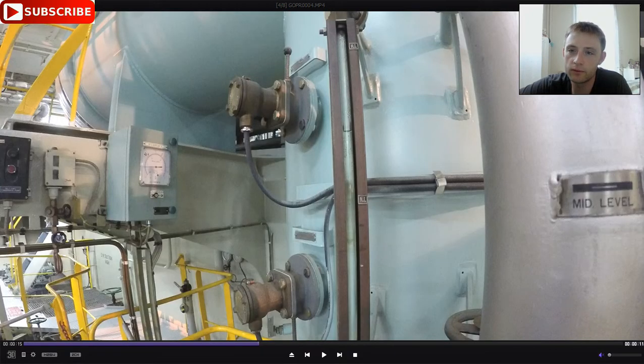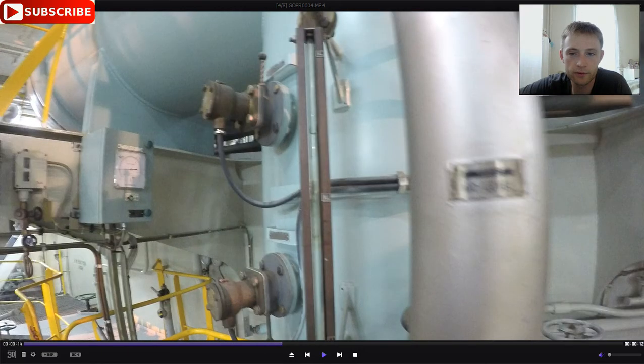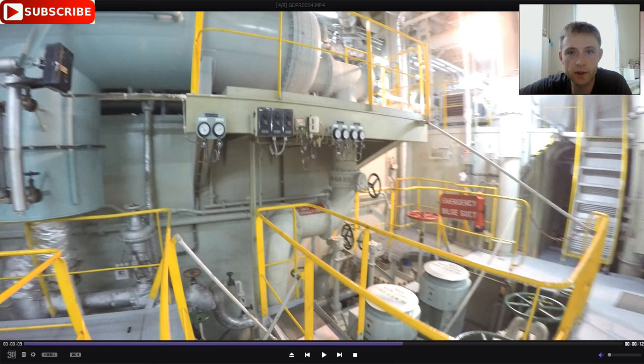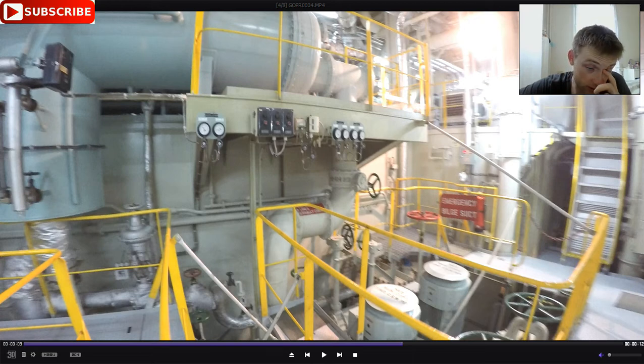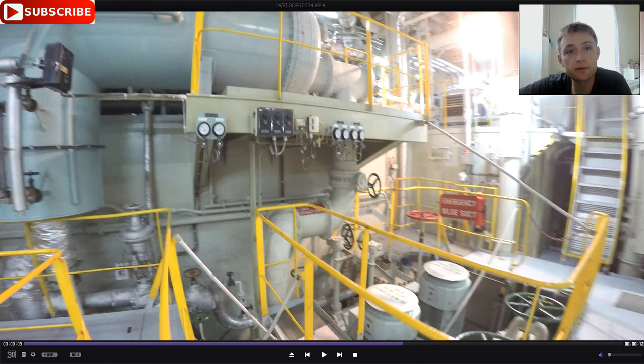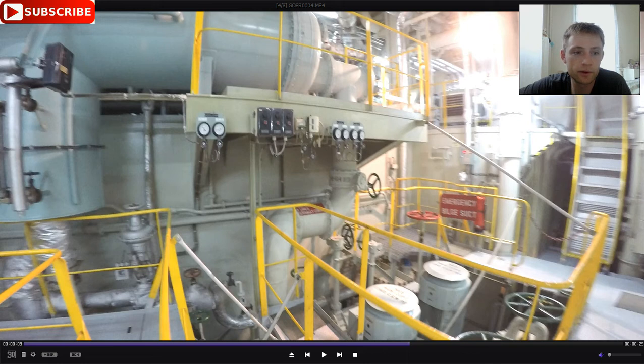We can see that we have a mechanical float here which regulates the level. From here, sea water is supplied to the condenser, passing through for cooling. The sea water is adjusted with one valve and supplied overboard. Inside there are tubes — on one side steam is passing, and the sea water passes through to cool it. As the steam cools down it becomes water — it condensates — and is sucked out by condensate pumps, two small pumps.